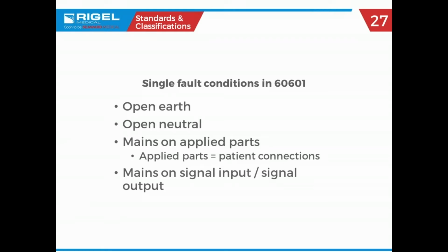Ultrasound machines have been damaged by doing reverse polarity testing, so that's kind of become a no-no. Here in the States, jumping forward a little bit, we do open ground as our single fault condition. That's the only one you have to do. So we do, as I said, open earth, open neutral, mains on applied parts.